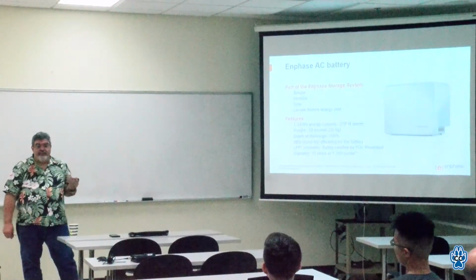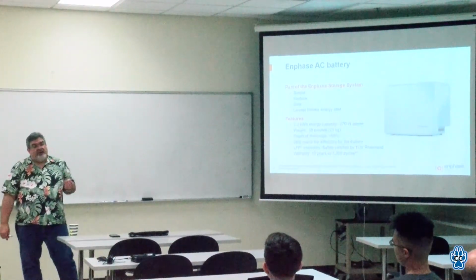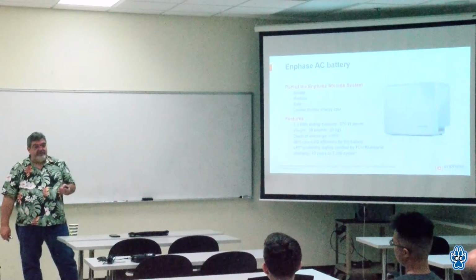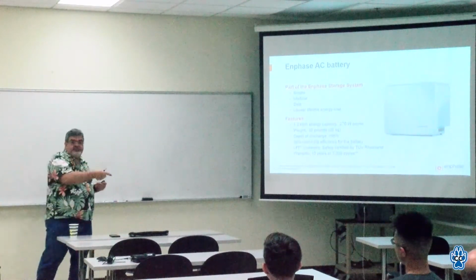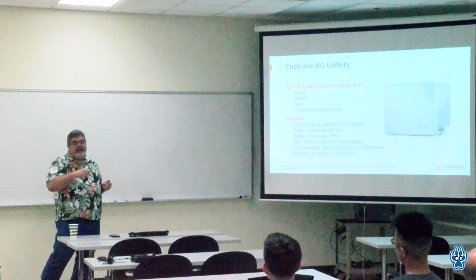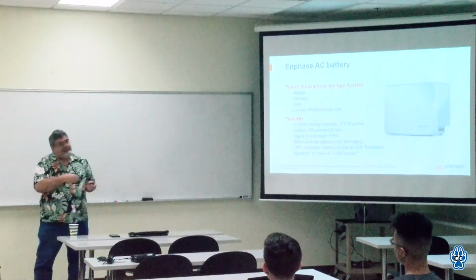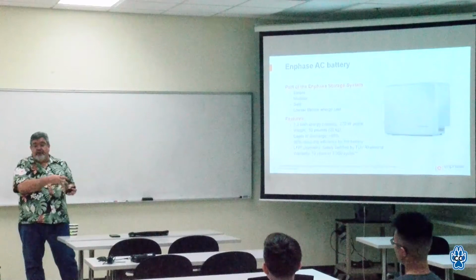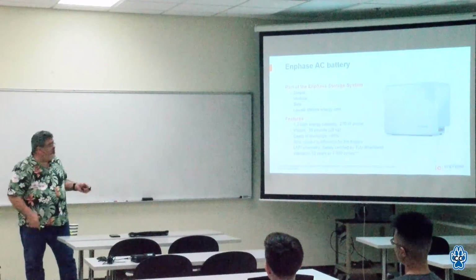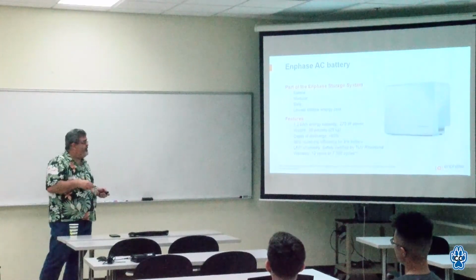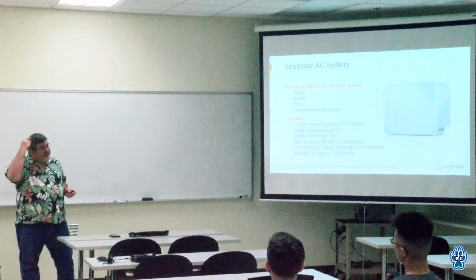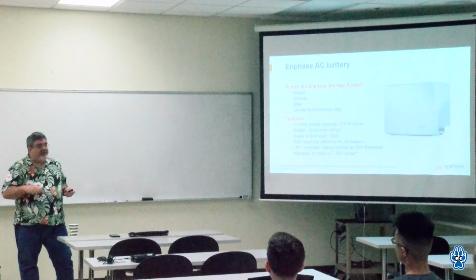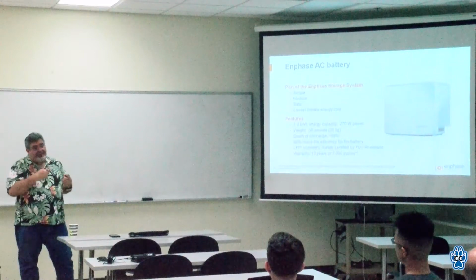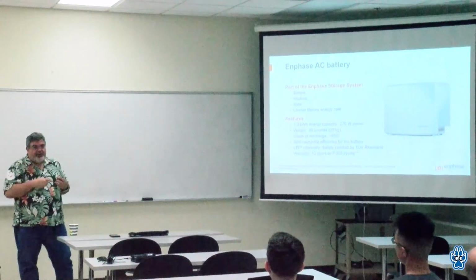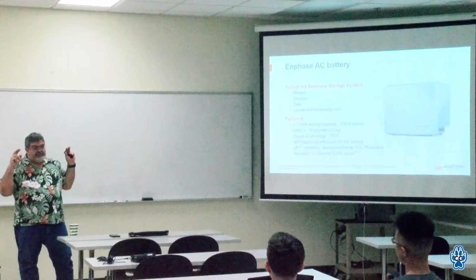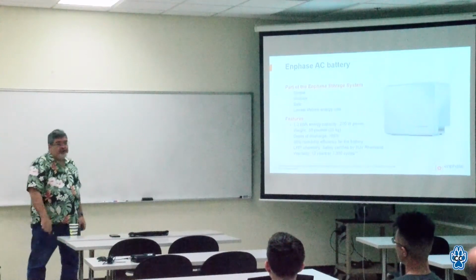You charge up your cell phone, what happens? It gets hot - that's lost energy, that's inefficiency. You put in X watts, and you're getting X minus that heat actually going into the battery, because part of that energy was lost. So there's an efficiency for charging the battery too, ours is about 96%. Overall, multiplying 97, 97, and 96, the overall round-trip efficiency is about 89% in and out.